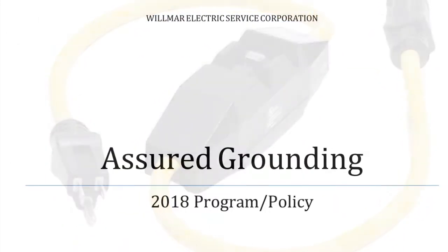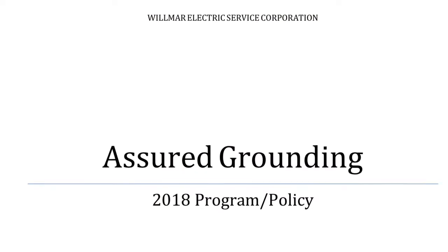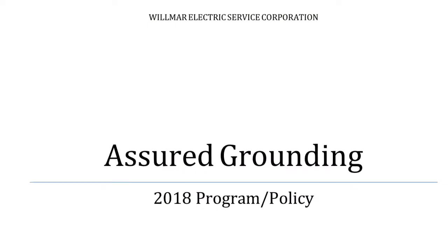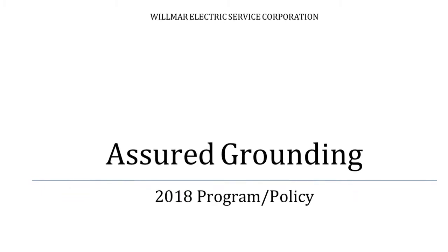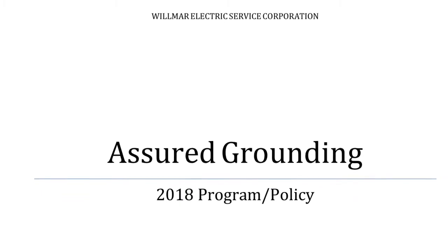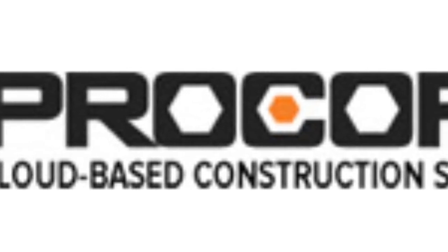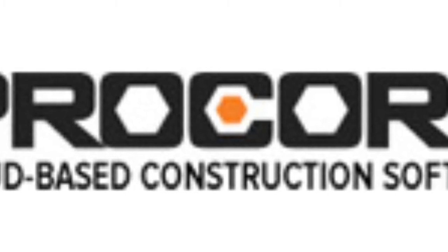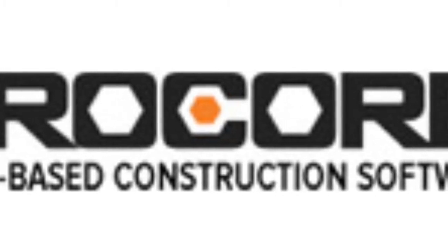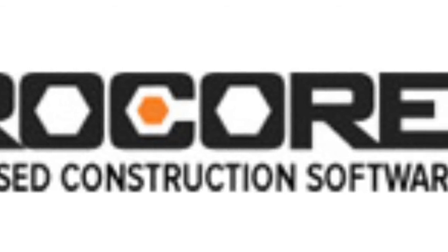Willmar Electric Service's Assured Grounding Program is an inspection program covering all cord sets, receptacles that are not part of the permanent wiring structure, and equipment connected by cord and plug. OSHA requires a written description of the program. This written description can be found in the Safety Reference Job on Procore. In addition, assured grounding procedures and color coding can be found in the Safety Reference Job on Procore. All employees have access to the Safety Reference Job.